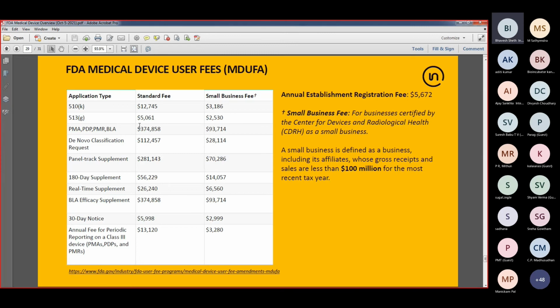Now, you also need to be mindful of the testing cost. Many of you might be aware that Intertek does a lot of electrical safety, EMC testing, a whole lot of other performance testing for medical devices. But there are several tests that Intertek currently doesn't perform: biocompatibility, animal testing, clinical testing. Most of these tests are not performed by Intertek. A lot of sterilization validation is also not done by Intertek.